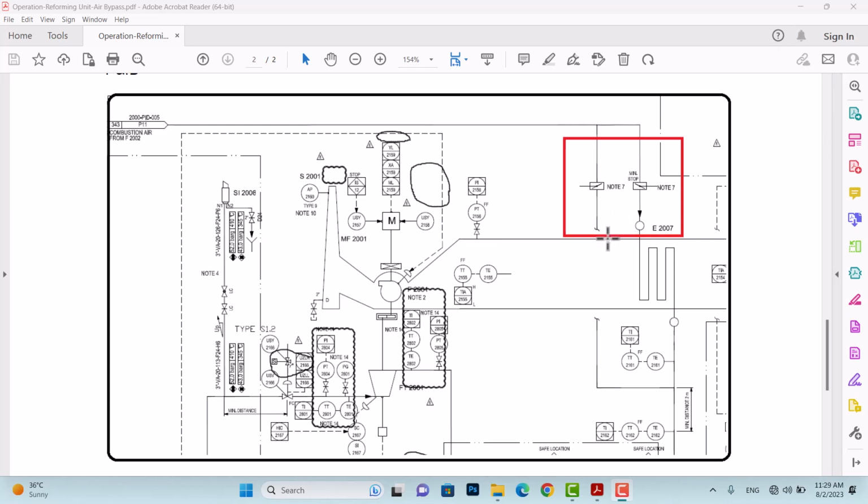Unfortunately, the operator was inexperienced and he changed the opening of the valve very fast, and all of it was done in a fast manner. So the temperature changed very fast, the density changed very fast, and the volumetric flow rate changed very fast.